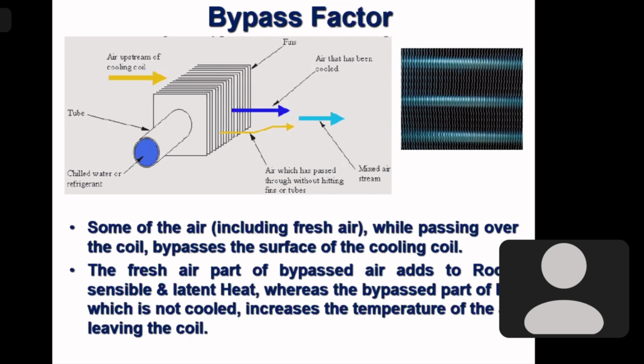So this bypass air contains two parts. One is the outside air, which we'll be considering in the heat load being directly added in the air conditioned room, and one is the return air. Return air temperature is 24. So some amount, 12%, of 24 degrees centigrade air comes straight through the cooling coil unaffected.